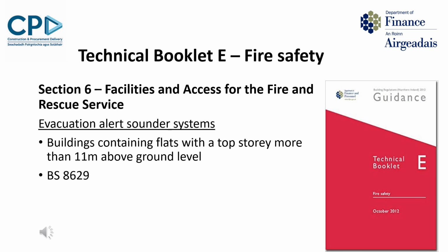So the British Standards Institution, BSI, has created a new standard for such systems, BS 8629, which is entitled the Code of Practice for the Design, Installation, Commissioning and Maintenance of Evacuation Alert Systems for use by fire and rescue services in buildings containing flats. It was published in 2019 and updated in 2023. So this is the standard that is cited in the TBE guidance for these systems to adhere to.